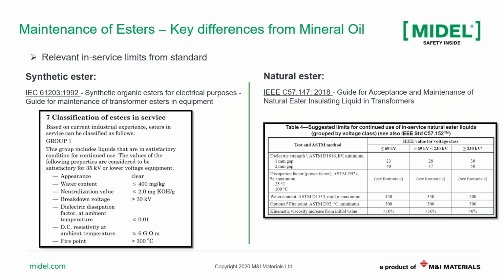In the table, you can see the classification of ester in service. This standard also applies to voltage levels of 35 kV and below, and you can clearly see the parameters to check are the appearance, the water content, neutralization or acidity, breakdown voltage, dissipation factor, fire point, and DC resistivity. These are for your reference. Equivalently, you have a natural ester standard, the IEEE C57.147, and depending on the voltage class, you have different in-service limits. So we need to familiarize ourselves with the differences in in-service limits between esters and mineral oil.